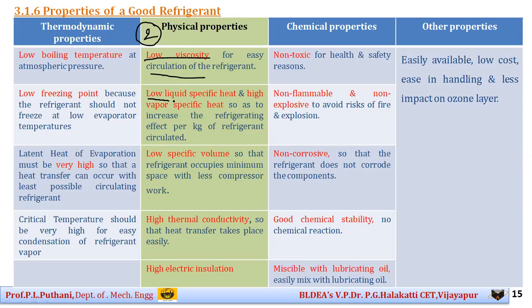The refrigerant should have low liquid specific heat and high vapor specific heat, which increases the refrigerant effect per kilogram of refrigerant circulated in the cycle. Also, in the compressor the vapor is compressed, so the specific volume comes into play. If the specific volume is as low as possible, the work required for compression is also less, and the refrigerant can pass easily through the entire network. So the refrigerant should have low specific volume.